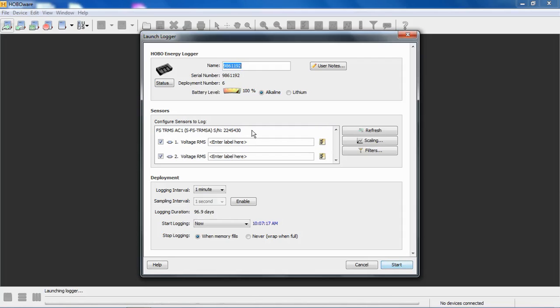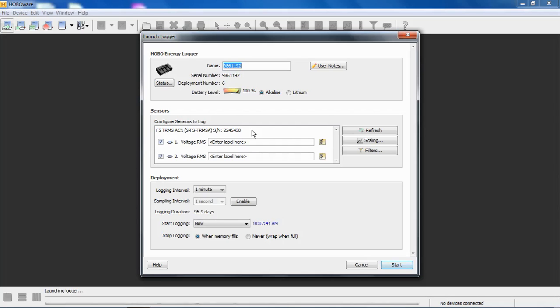It makes no difference as to where those modules are physically plugged into the top of the logger. They are aligned in the data and in HoboWare by serial number of the module or of the sensor. That's the same for smart sensors. If you plugged in your smart sensors in what you thought was slot number one, it really makes no difference. It's a bus. HoboWare assigns or aligns them by serial number, not by physical location.